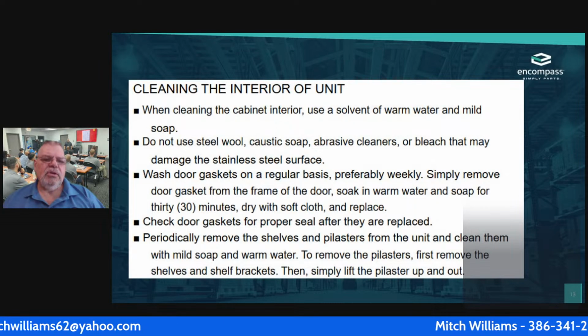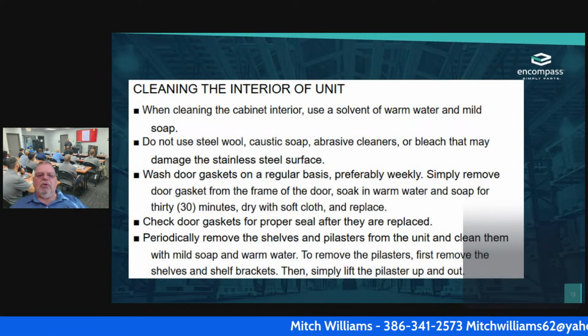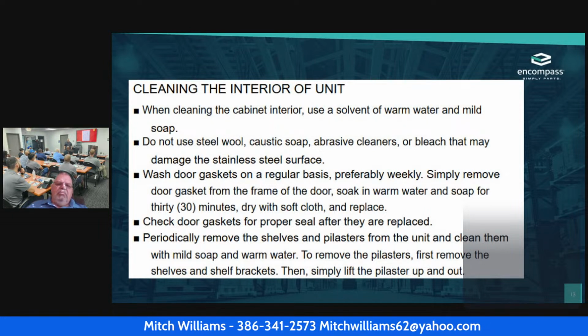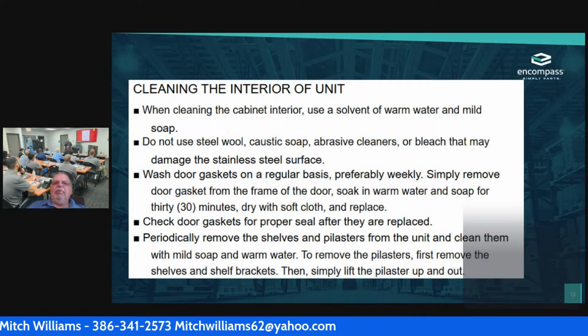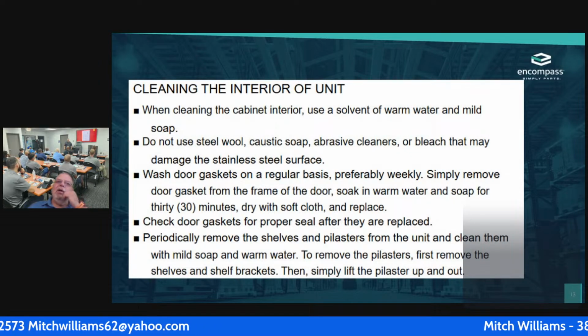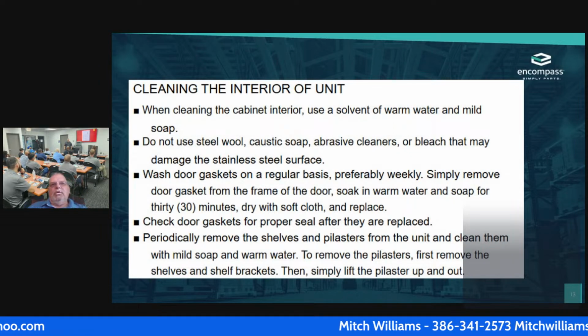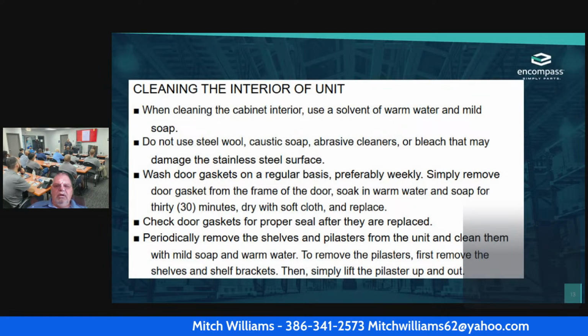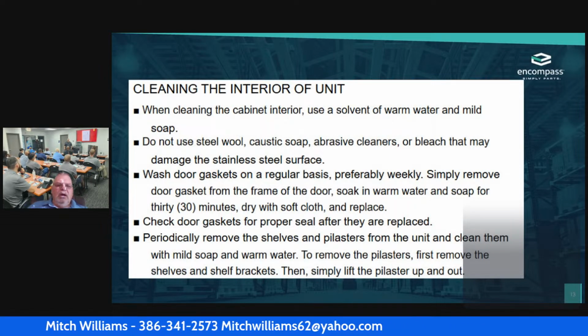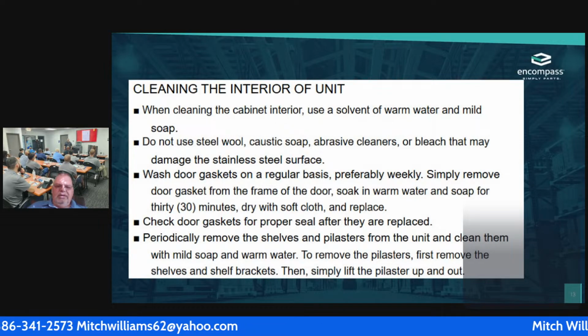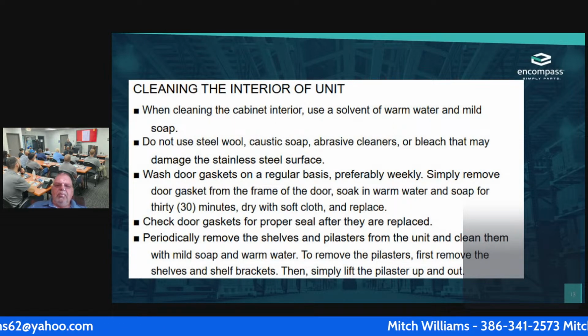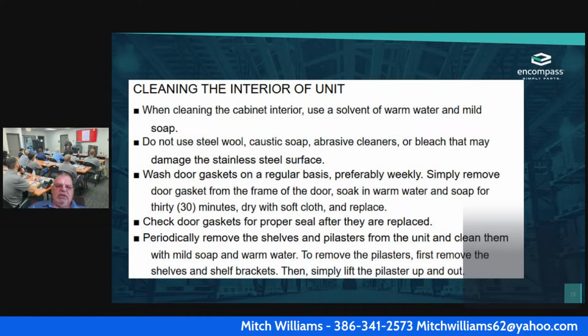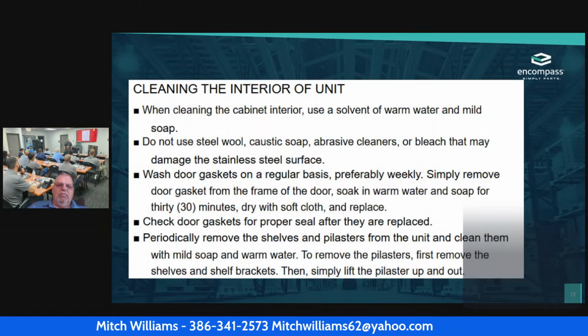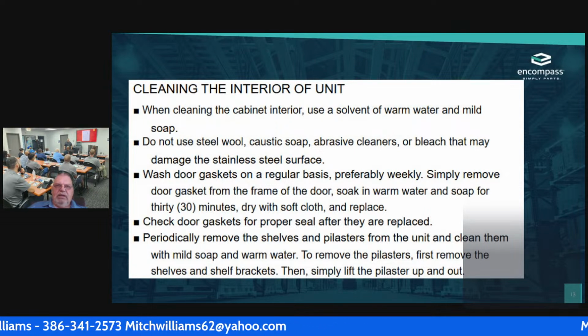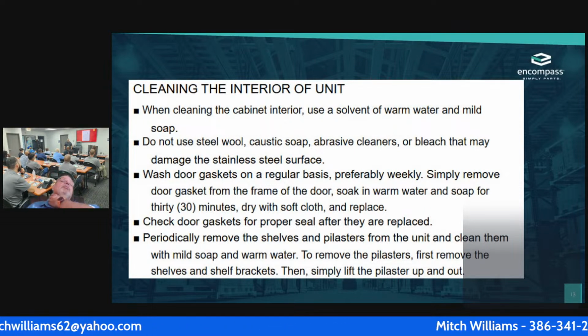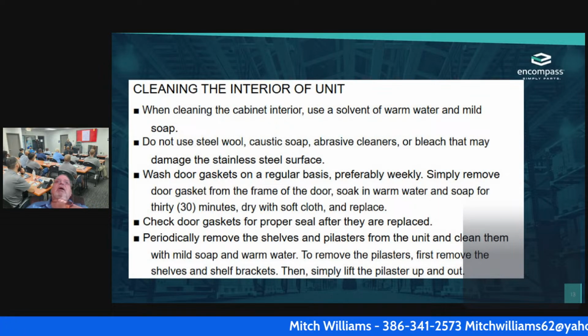Okay. Interior of the unit. When cleaning the interior cabinet, I'm going to use a solvent of warm water and mild soap. My personal favorite is Dawn. I figure if it's gentle enough to use on a duck, I can probably use it on the interior of a unit. Don't use steel wool, any kind of caustic soap, abrasive cleaners, or bleach that may damage the stainless steel surface. I have seen somebody that tried to use 100% bleach. They didn't even cut it. It will damage the unit.